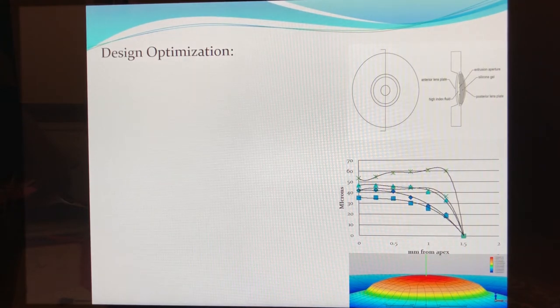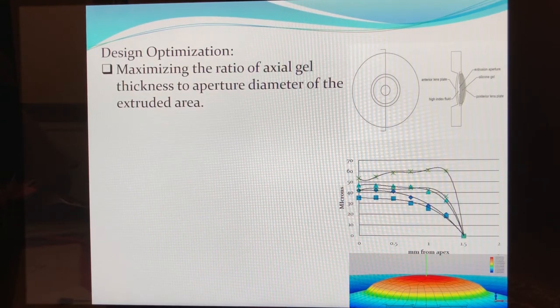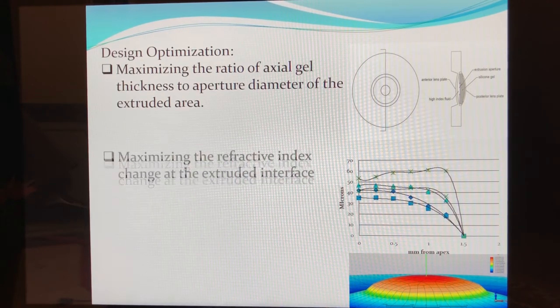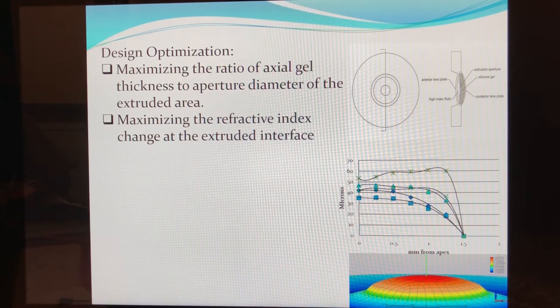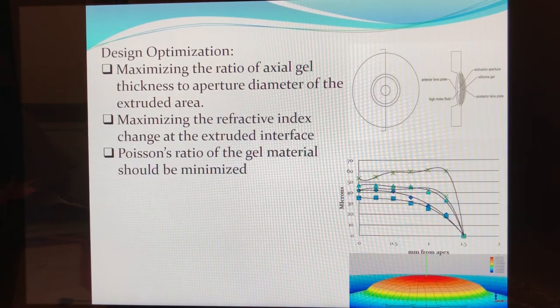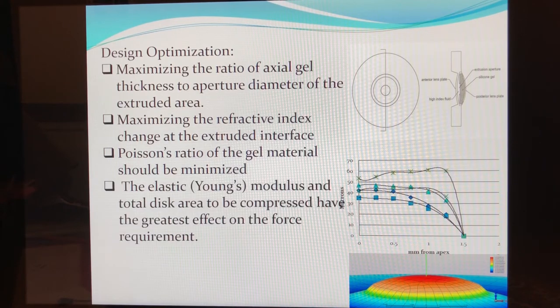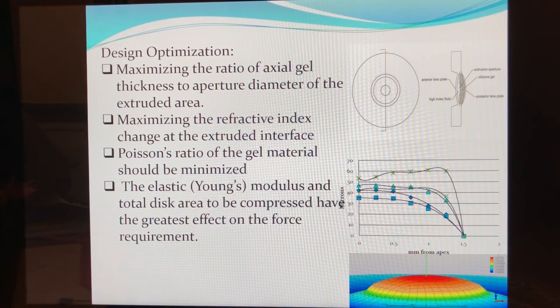We can now optimize our design relating optical, dimensional, and mechanical design parameters to the output metrics. We found that maximizing the ratio of the axial gel thickness to aperture diameter of the extruded area optimized the design. In addition, maximizing the refractive index change at the extruded interface optimized the design. Poisson's ratio of the gel material should be minimized. The elastic Young's modulus and the total disk area to be compressed have the greatest effect on the force requirement.